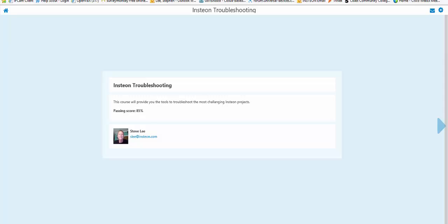This was causing the installation to have some marginal results. At times when you would push a button to turn on a bunch of lights, sometimes they'd all go on, but then a few of them didn't go off — and it was related to the high level of noise that was created. For quite a while they worked on trying to figure out where the noise was coming from, and I ended up going out there to help them with this project.